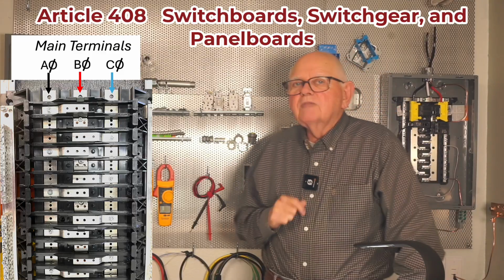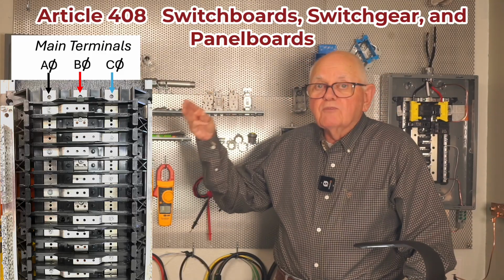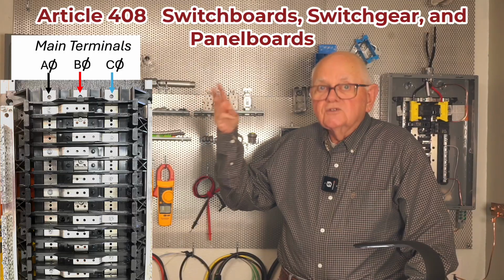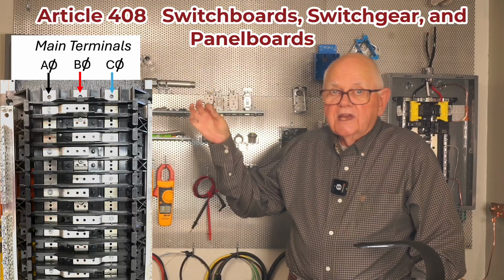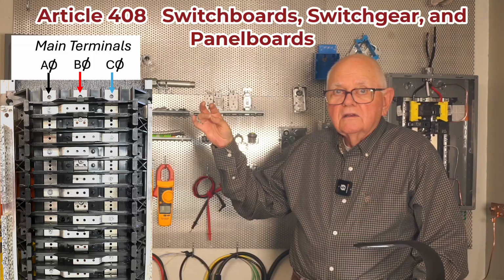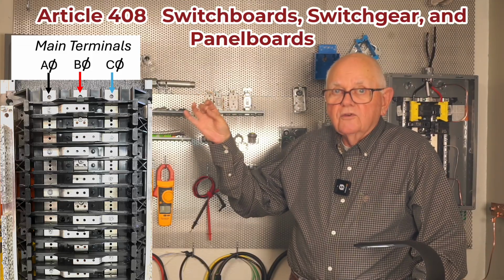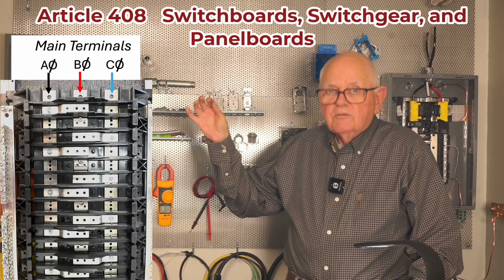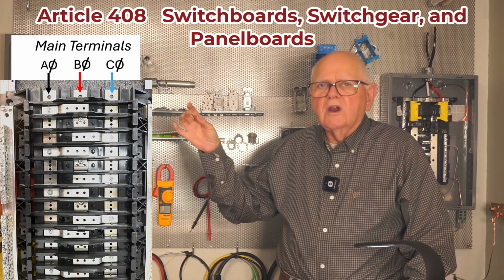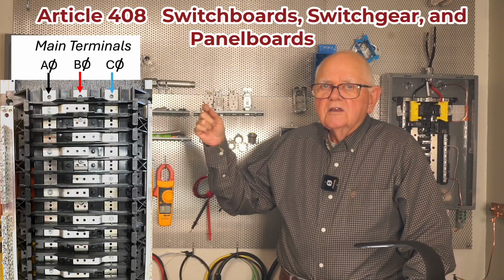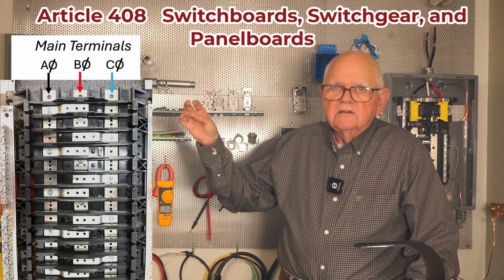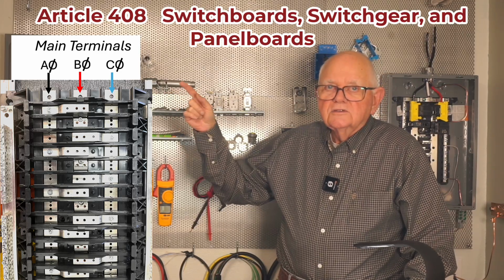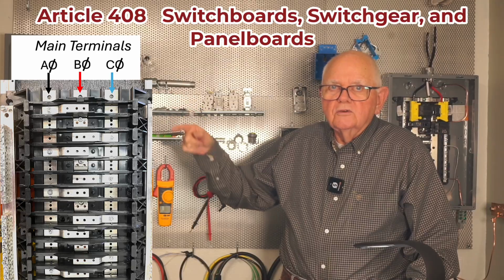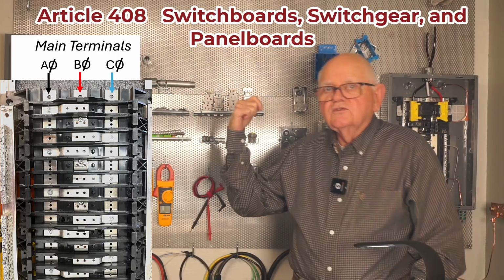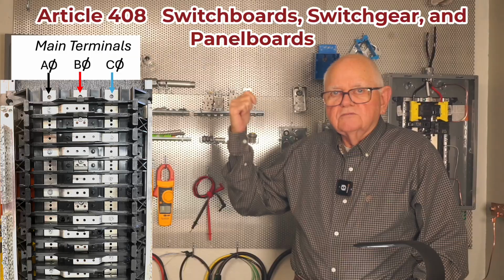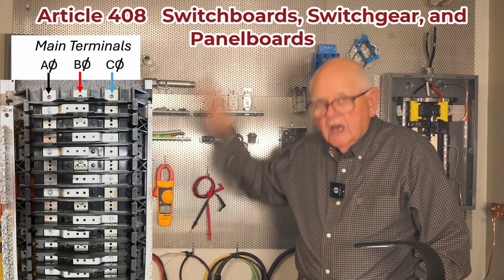So what I just described to you, with those 3 individual single-pole breakers, I have phase A, phase B, phase C. I have breaker 1, breaker 2, breaker 3. And if I'm color-coding them by industry practice, not required in the code, but let's say I use black and red and blue for A, B, and C. So what do I have? I have circuits 1, 3, 5, black, red, blue, A, B, C. And the same is true on the opposite side.